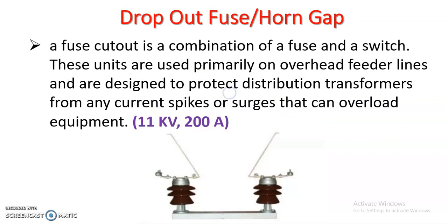consumer. Then next is dropout fuse, or which is also called as horn gap. So it is a combination of fuse as well as switch. So these units are used mainly primary on a overhead feeder line and designed to protect the distribution transformer. If current spikes or surges occurs, it will open. These two contacts will get open and this arc will split it, as it is horn gap. The rating of dropout fuse in case of plinth mounted substation is 11 kV and current rating is 200 ampere.